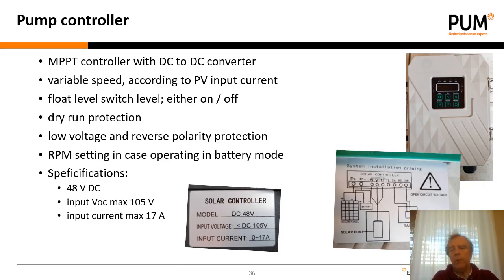So here is the pump controller that we used in the Benin example. It is an MPPT controller with a DC to DC converter. Remember that the MPPT controller is a very efficient controller, where it gives you the optimal input while the conditions of course vary with the solar, if clouds float by and so on, and the MPPT controller is efficient with that. It supports variable speed according to the PV input current. It contains a float level switch which can be on and off, a dry run protection, low voltage and reverse polarity protection, and you can set the rounds per minute in case of battery mode.